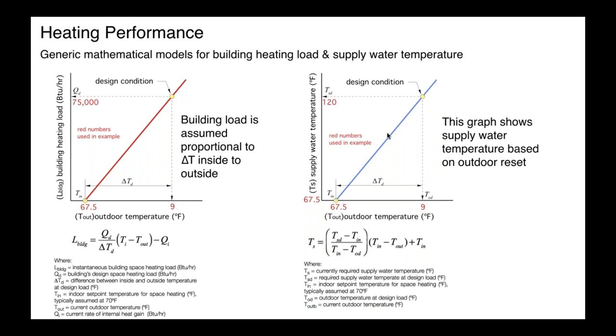And this is really important with heat pumps because, as we've talked, the heating capacity and the coefficient of performance are strongly dependent on outdoor temperature. So if we can lower the water temperature that our hydronic system operates at as it gets warmer outside, we can force that machine into much higher performance as compared to, for example, setting up controls that constantly require the machine to produce 120 degree water. Either one of those control strategies is possible, but the outdoor reset strategy is definitely going to produce better savings, and I'll show you that.